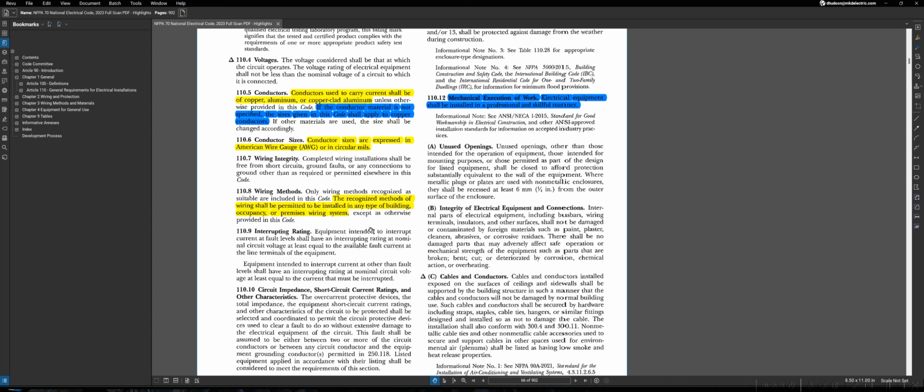And to go with that as well, both in the case of the NEC as well as in the real world, if the type of conductor is not stated for something, then you always assume that it is copper. As we'll see later, equipment has to be identified for what type of material you're allowed to use to connect to it. So for instance, if you want to land an aluminum conductor under a lug, that lug would have to have a stamp stating that it could accept an aluminum conductor. If that lug does not have a stamp specifically stating that it is acceptable to use aluminum with it, you can only assume that copper is the only conductor allowed to be used with it.